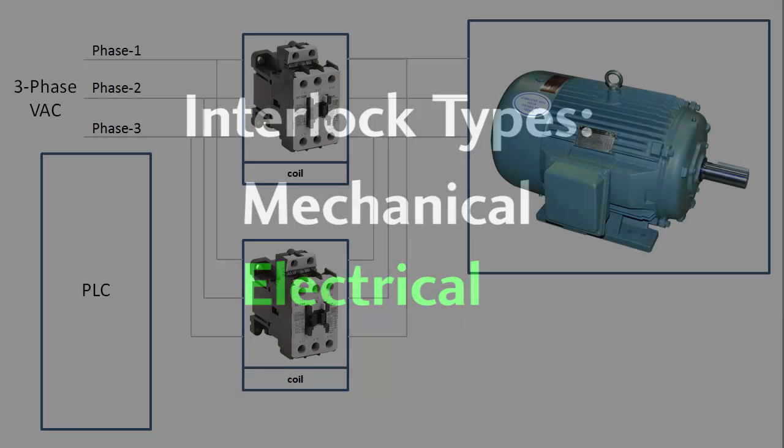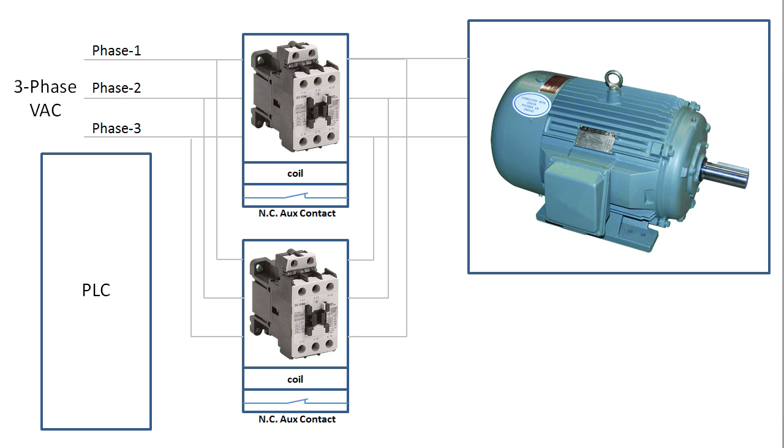The other way to interlock contactors is with an electronic interlock. You add a normally closed AUX contact to each contactor and wire them like this. So if this contactor is active and this AUX contact opens, there is no way that coil power can get to the other contactor. Likewise, if this guy is active, coil power can't get to this contactor.